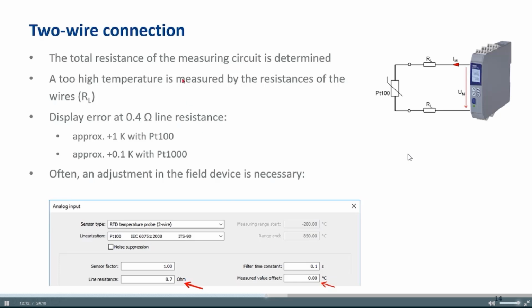Okay, but with the two-wire connection, if you have a long cable and a PT100, for instance, you have a big offset and you need to make this offset correction. This takes effort. And on the other hand, sometimes people don't do it in the plant, and maybe finally we have trouble because of this.